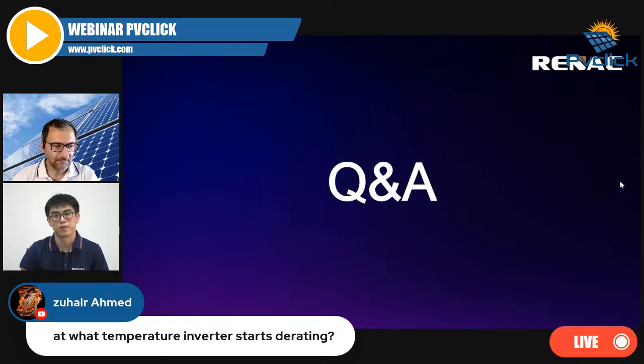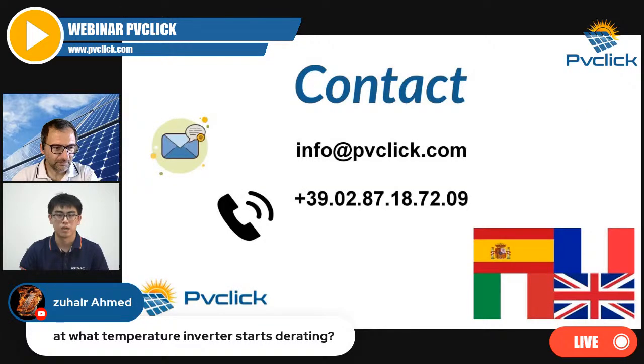We have units inside our inverter to measure the temperature. If the temperature reaches 70 degrees, the inverter will derate, and for each 1 degree increase, it will derate 10%. Once the inverter reaches 80 degrees, it will stop working.